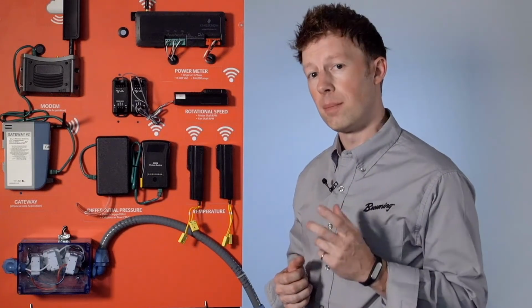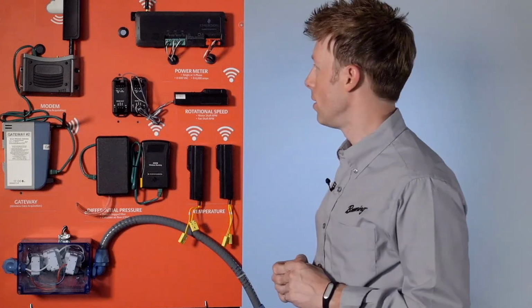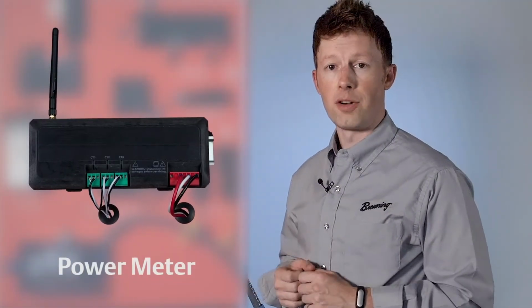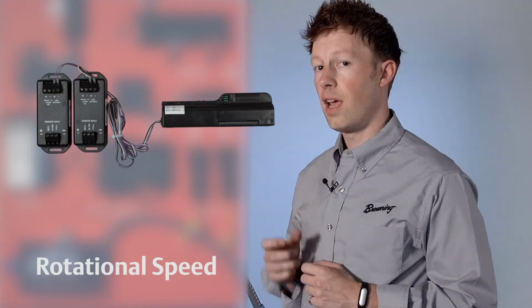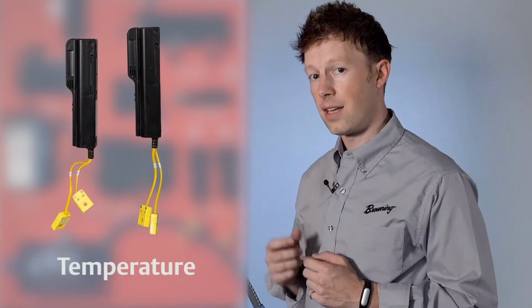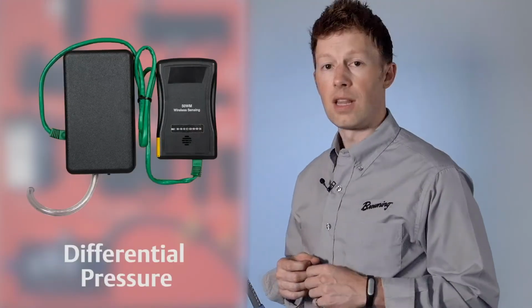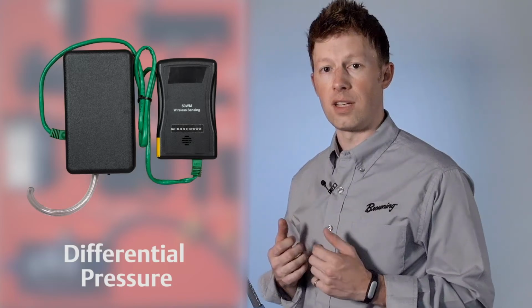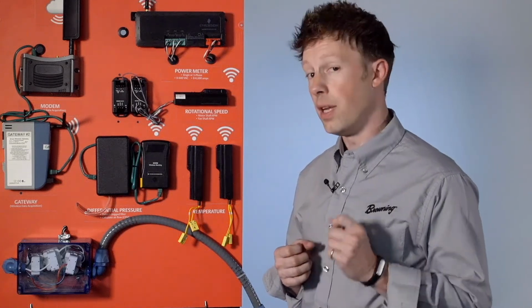And now what we're going to do is we're going to talk about the process of doing energy validation at a customer's facility. Now let's take a quick look at the field diagnostic equipment we have available for being able to monitor the energy consumption at the customer's facility. We have the power meter. That allows us to monitor the kilowatt consumption of the motor. We have rotational speed sensors. That allows us to monitor both the driven and the driver shaft speed. We have temperature transducers. That allows us to monitor both the internal and external temperatures. We have pressure transducers. That allows us to monitor the differential pressure so that we can calculate the CFM output of the fan. And from there, we can take all this data and wirelessly transmit it through an independent network to the Power Transmission Solutions engineers for analysis.